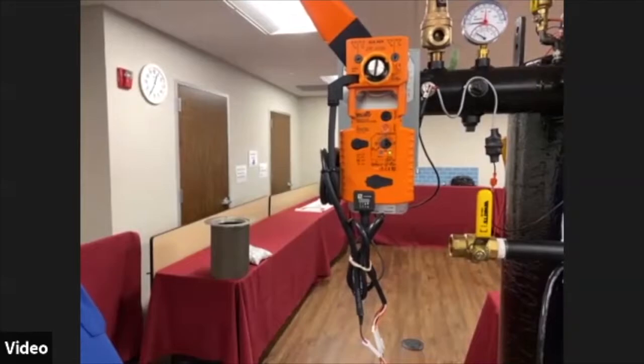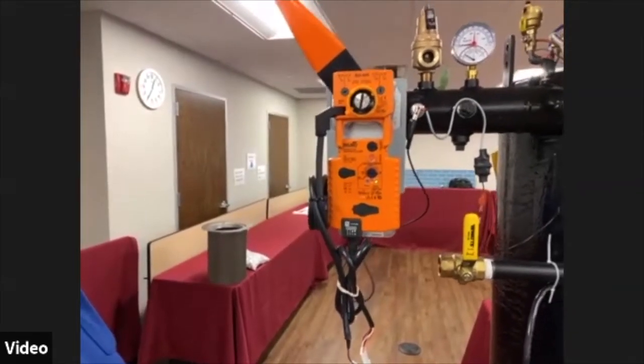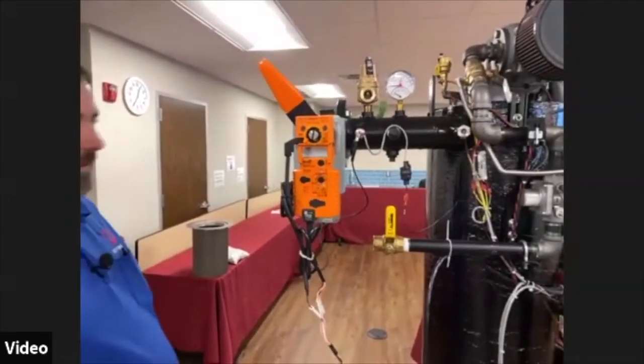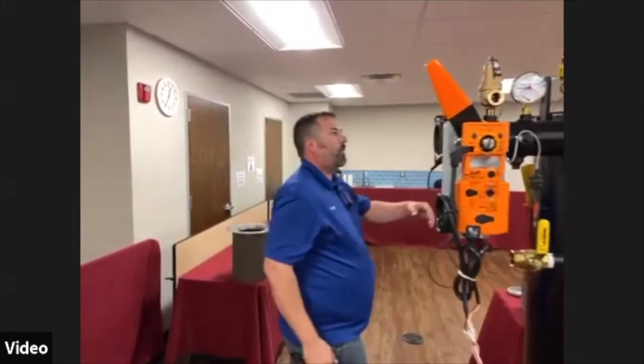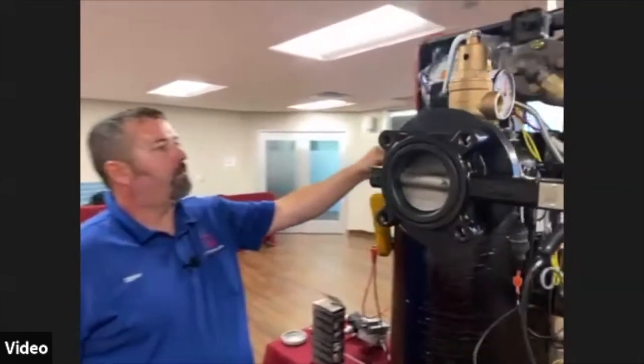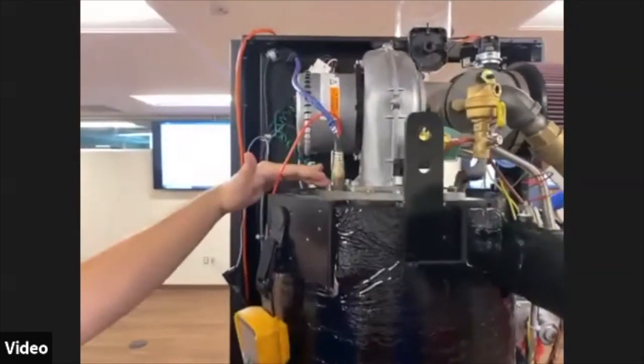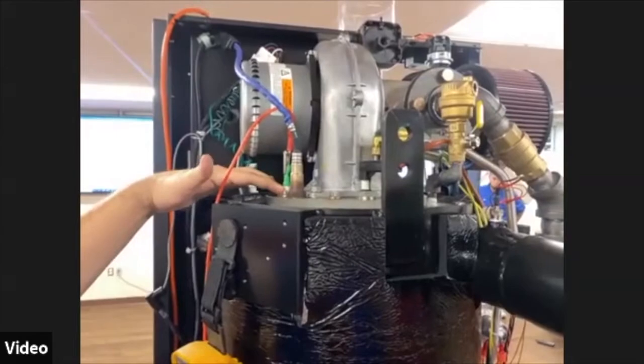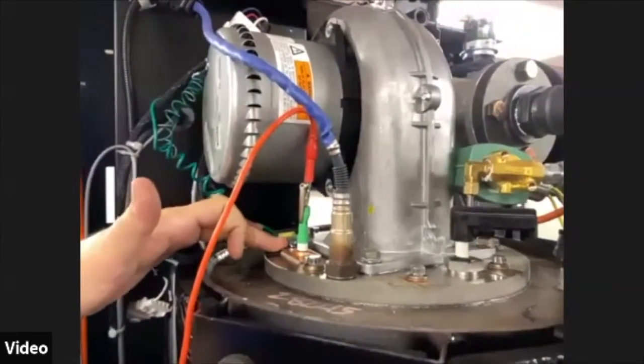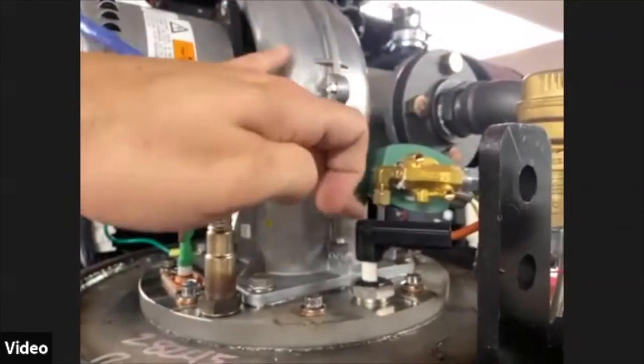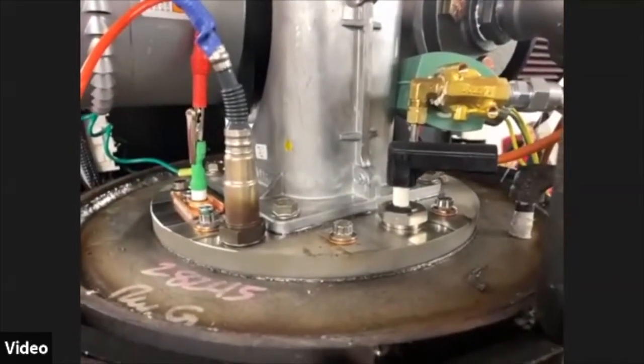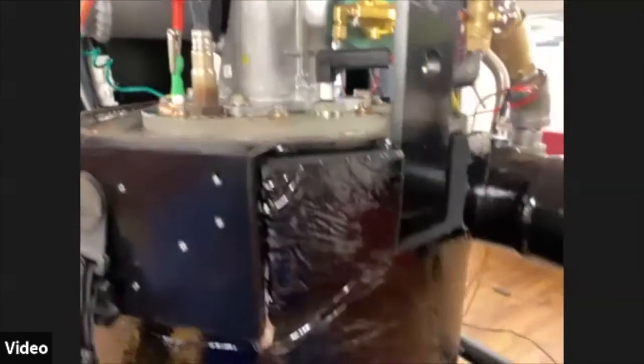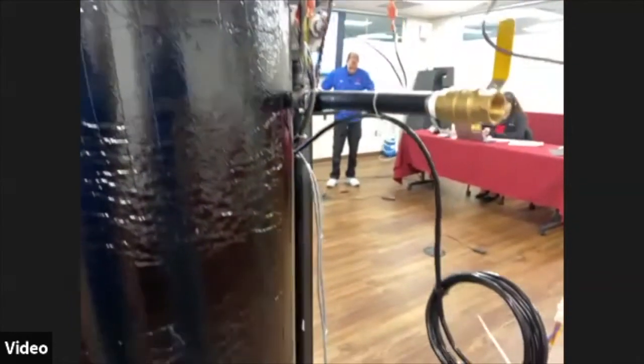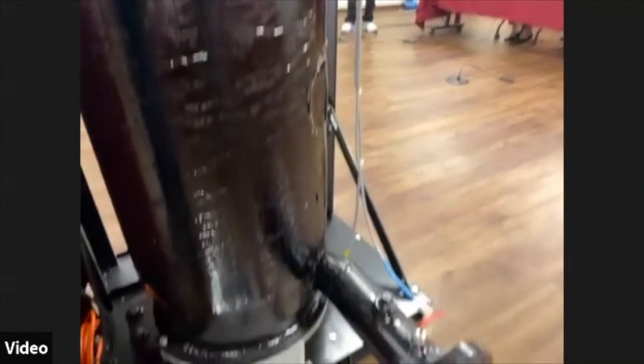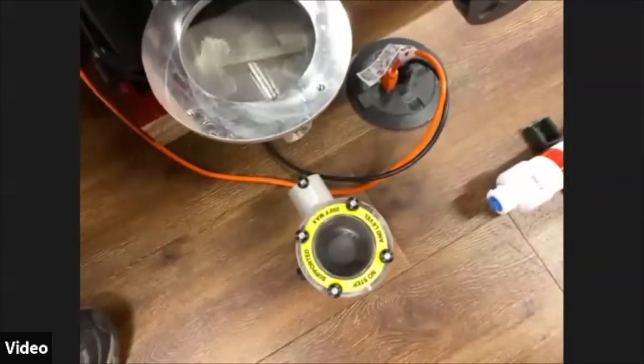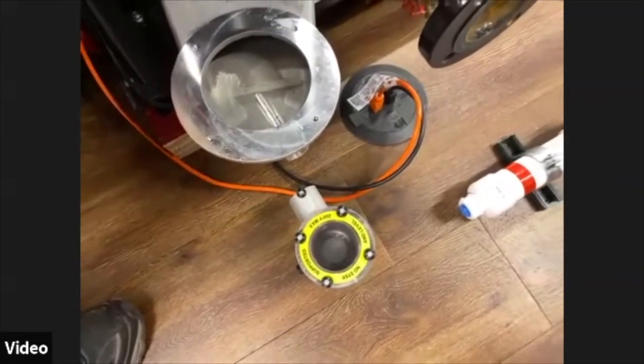Semi-annually, Aerco would like you to check the flame sensor and igniter and clean the condensate trap, as Ron pointed out over here on the top. So semi-annually, you can clean the flame sensor, which is just the 2 Phillips screws, and the screws are offset, so you can't put the sensor in backwards. There's only one way it'll fit. And same with the igniter. You can take off your compression fitting and your plug and pull the igniter out and clean it. And also semi-annually, I would clean the condensate trap, because depending on the environment down here, it can get a little dirty. Definitely want to clean the condensate trap and neutralizer semi-annually, especially if the boilers are running dehumidification and running all summer long. You'll definitely want to do that twice a year.